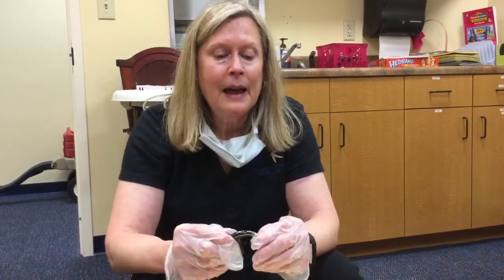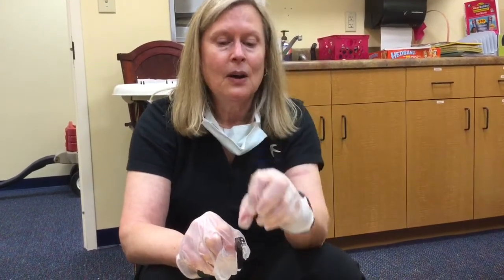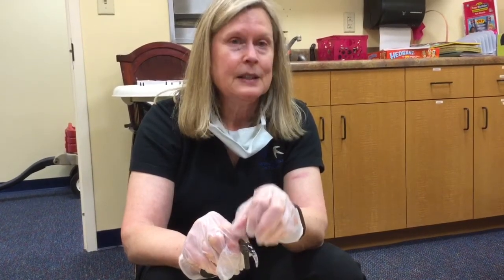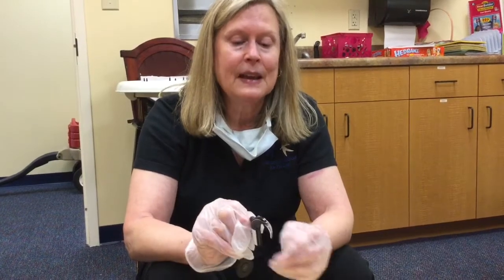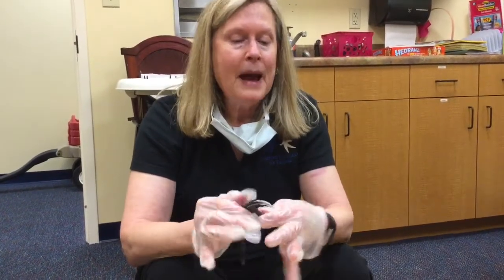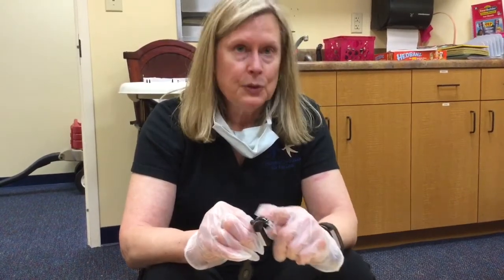If your child has bilateral implants, a pretty easy way to troubleshoot, like if you're seeing a flashing light on one ear and it's green on the other ear, the processor on the other ear is green, then you know everything on that ear is working fine. So you can take the cable coil from that side and put it on the side that's flashing orange. And if that solves your problem, then you know you need to go find your spare cable coil for the ear in question. So that's one nice thing that you can do. Cable coils and batteries are interchangeable. Processors are not. So you can't put a right processor on a left ear and expect it to work.